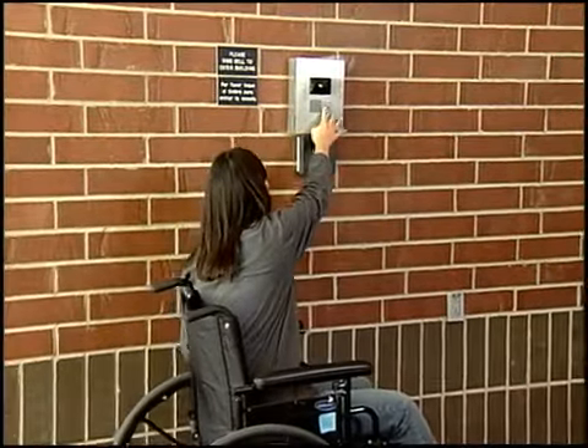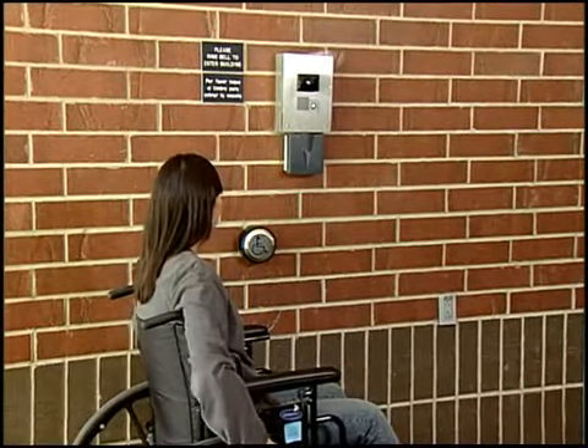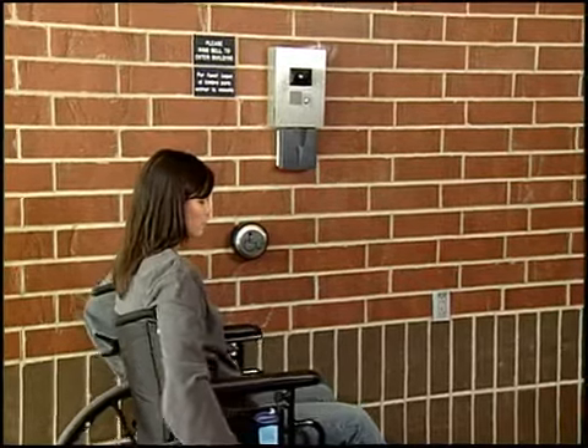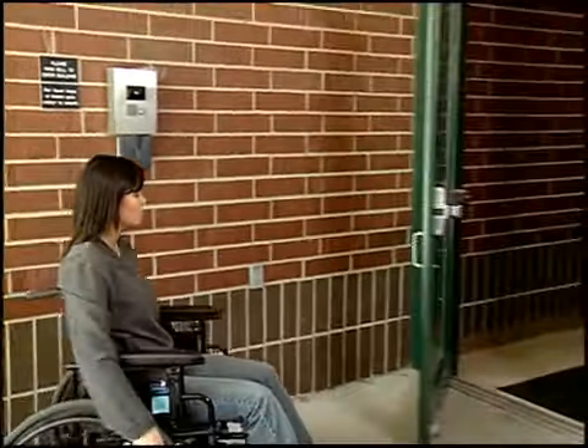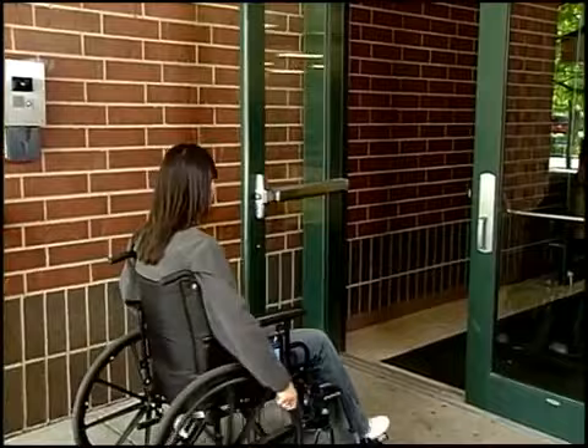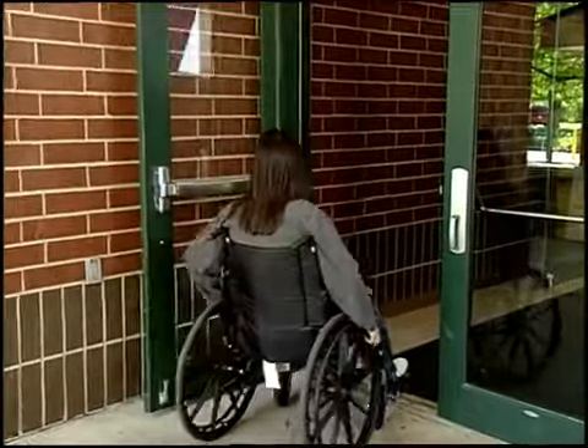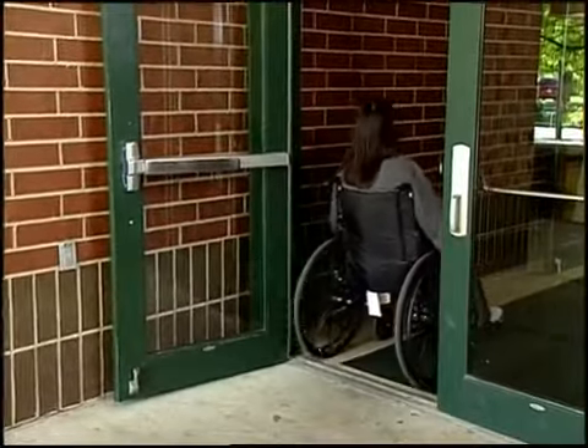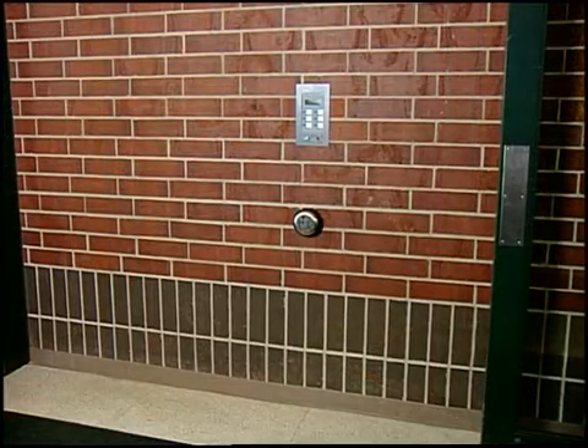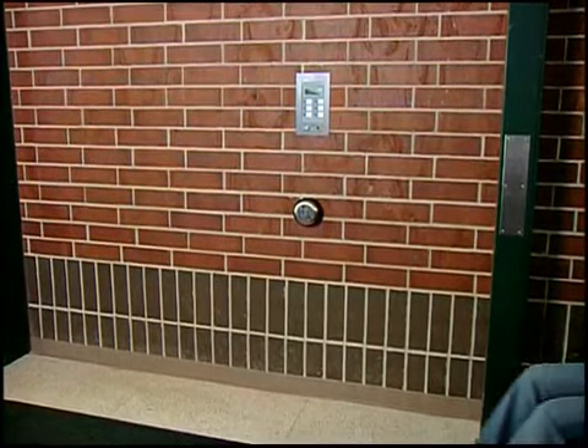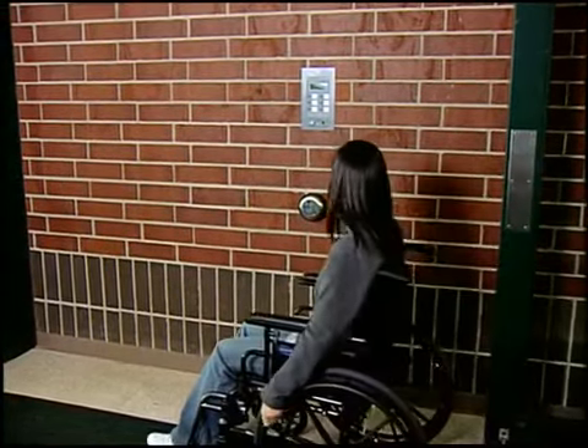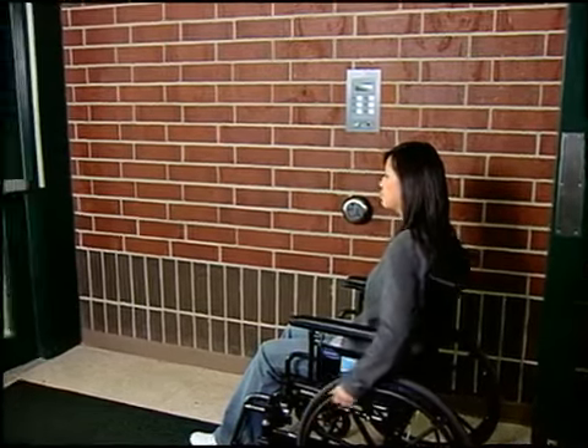When a visitor requests access through the intercom system, the internal release button unlocks the door and activates the actuator simultaneously. The visitor can then enter manually or press the actuator button to open the door. For safety purposes, the actuator in the vestibule remains live at all times to ensure that people can always exit the building in case of emergency.